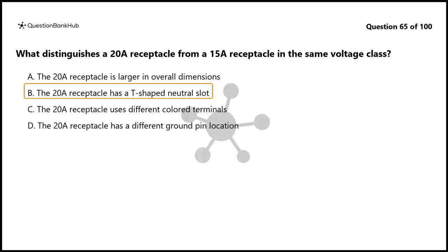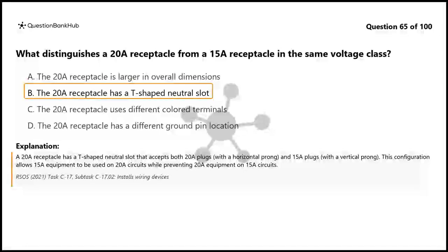The correct answer is B. The 20 amp receptacle has a T-shaped neutral slot. A 20 amp receptacle has a T-shaped neutral slot that accepts both 20 amp plugs, with a horizontal prong, and 15 amp plugs, with a vertical prong. This configuration allows 15 amp equipment to be used on 20 amp circuits while preventing 20 amp equipment on 15 amp circuits.